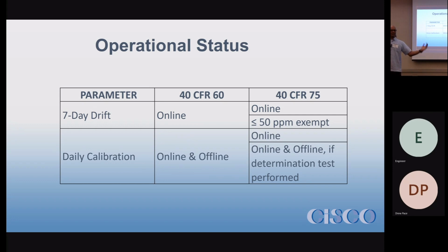And this is a one-time test you do, and it lasts forever until you change out the analyzer. For those of you who have had us involved with your certification, we typically generate this for you as part of certification because we're already looking at data. It's during the testing period, so it's no big deal for us to just go ahead and add that so that you have it. And whether you use the offline CALs or not, that's your business.